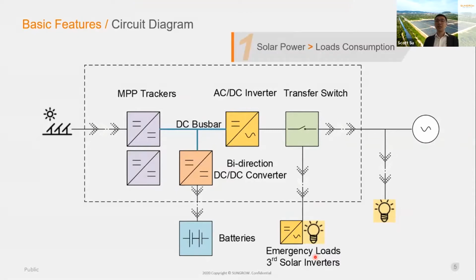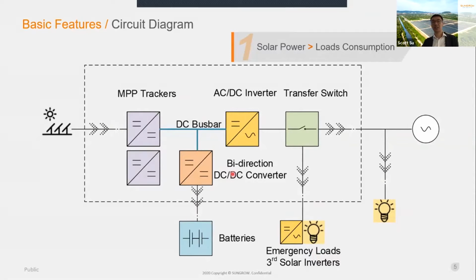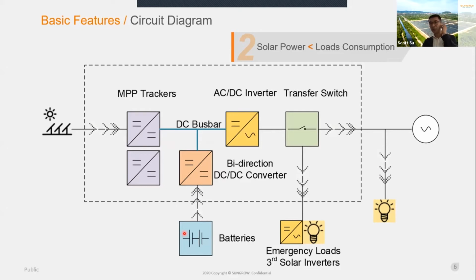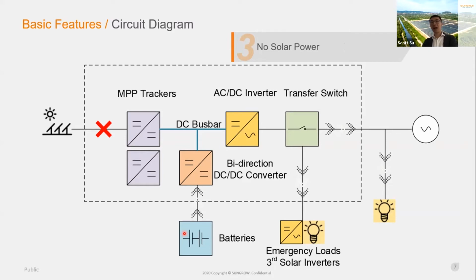Okay. So the first scenario you can see here is when the solar power is very sufficient. And you can see here, this is the PV arrays. The energy will go through the maximum power point trackers to the main DC bus bar, and then go through the AC to DC inverter to the AC side to supply the emergency loads and the other loads. Secondly, the rest of the solar energy can charge into the batteries here, okay? The second scenario is when the solar power is not sufficient and the battery can discharge to offset the load consumption. The third one is such as at night, the solar power is not available, but the system can still work. We can discharge the battery to supply the house loads, okay?